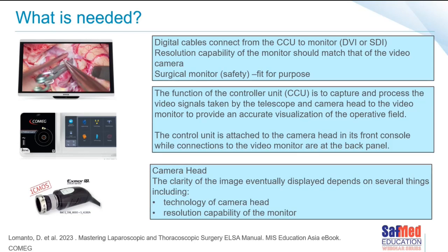The function of the camera control unit is to capture and process the video signals that are received from the telescope and the camera head, put that on display on the video monitor to give you accurate visualization of the operative field. The camera unit, of course, is attached to the camera head in the front console, and at the back normally is all the connections to the video monitor. The digital cables connect from the CCU to the monitor using two particular formats. You can use a DVI, which is a digital video interface, or an SDI cable system, which is a serial digital interface. The resolution capability of the monitor, as we said earlier, should match that of the video camera.